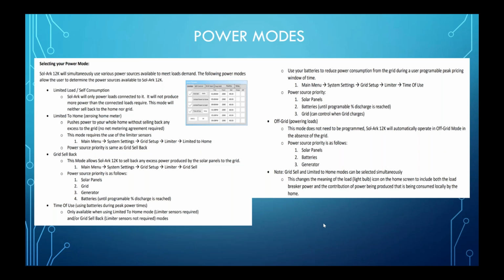And then finally, we do have Time of Use. Time of Use is a big one, and one that we do see used quite often. This allows you to prioritize, or at least set different timestamps, to discharge the batteries during specific hours. For instance, if you have peak hours or peak demand hours, then you can set a certain amount of the batteries to be used to prevent that peak from happening, or to prevent from using the grid power even at nighttime. So it's very customizable, very helpful for people that want to take advantage and don't mind using a little bit of their battery every day to help savings.